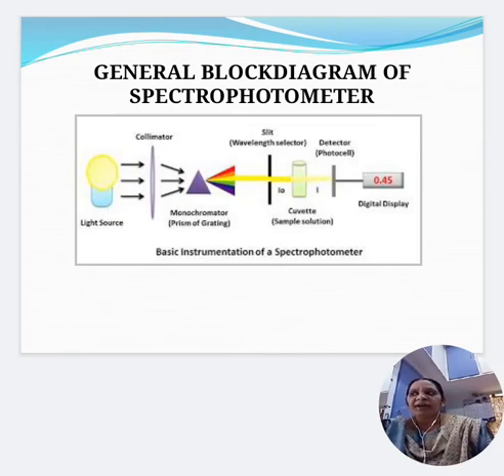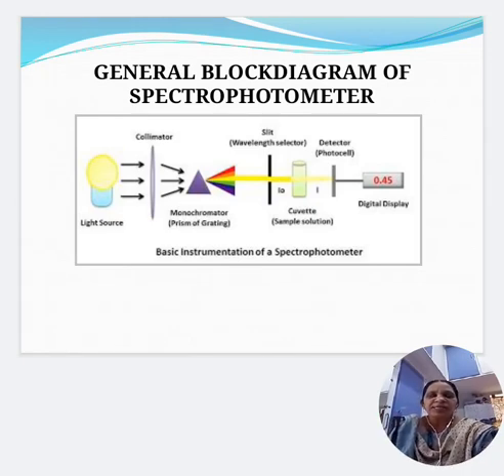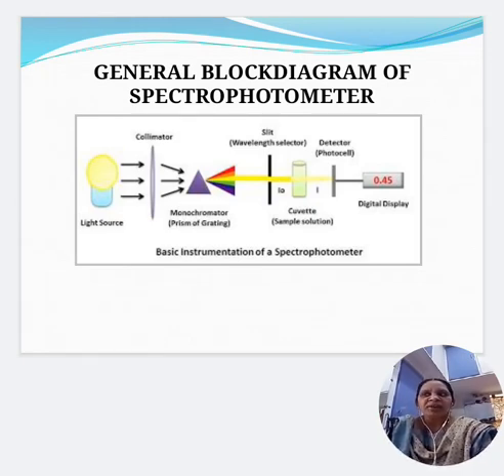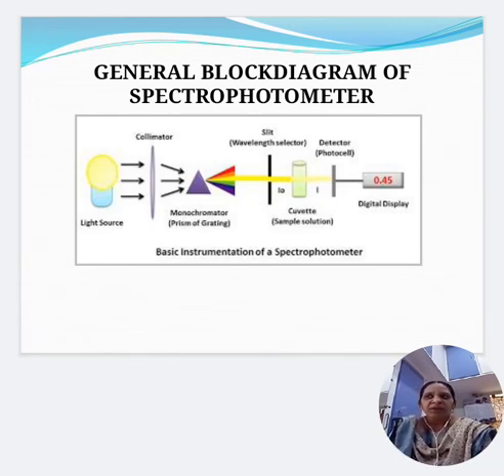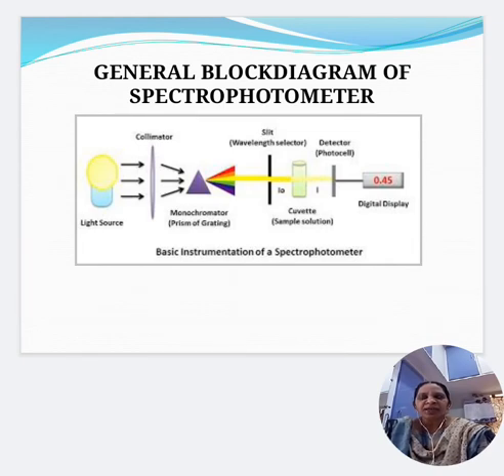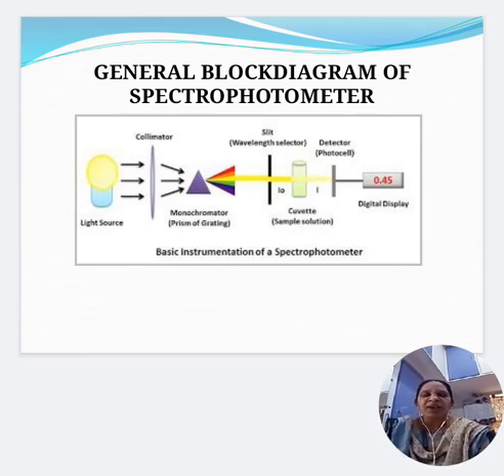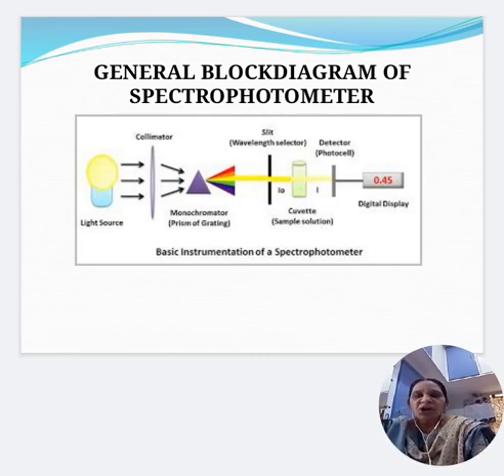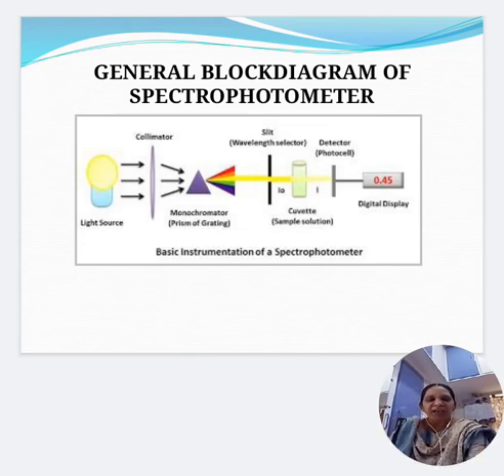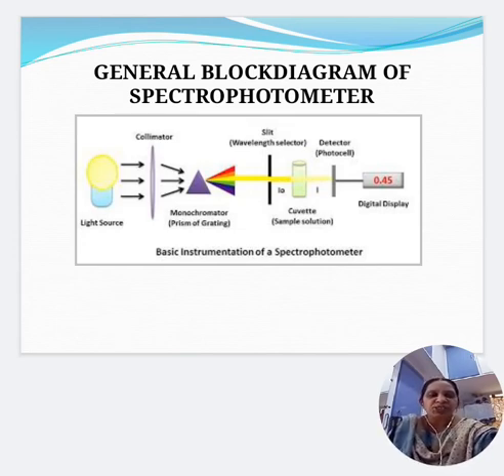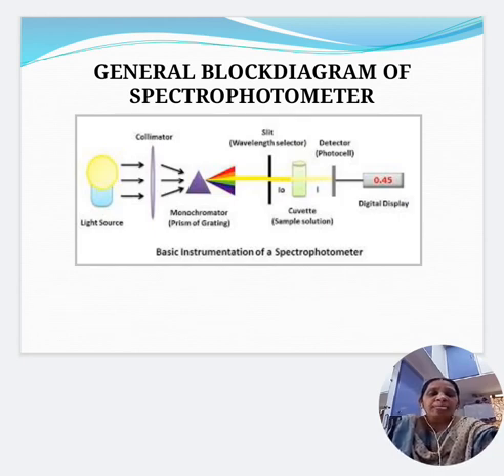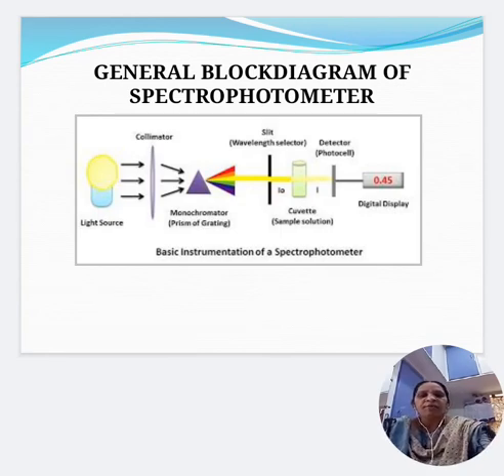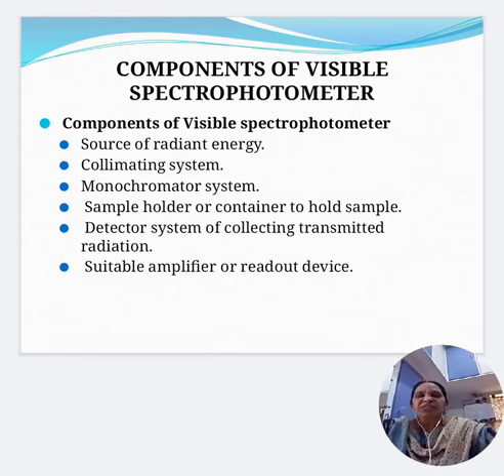The general block diagram of a spectrophotometer consists of a light source or radiant source, a collimating system, a monochromator which may be a prism or a grating, then the entrance and exit slit, the cuvette or sample holder, the photodetector, the detection system, and the display system or readout device.